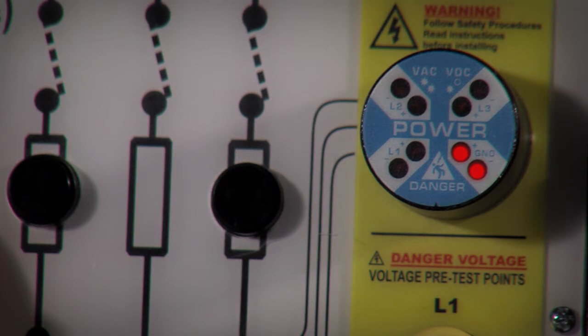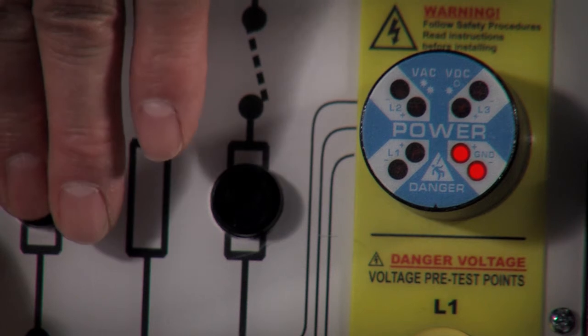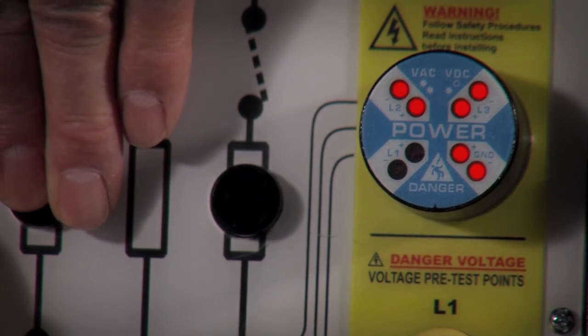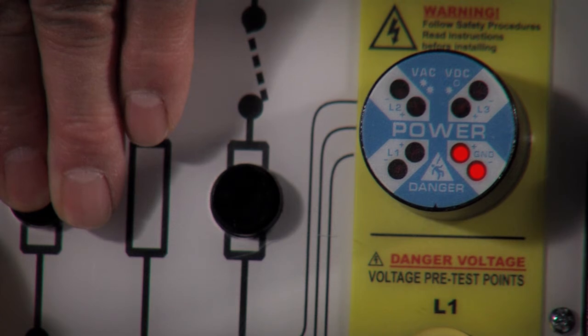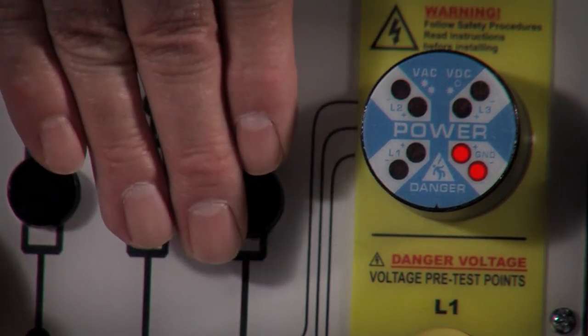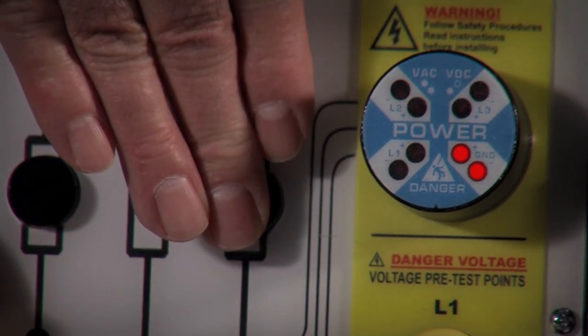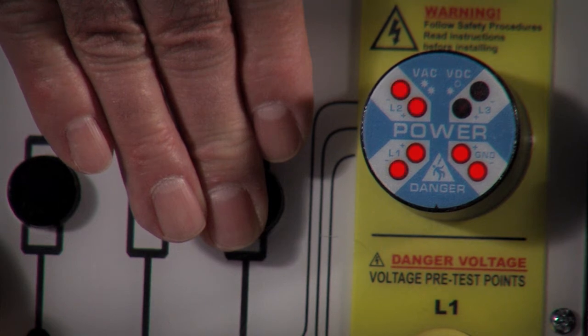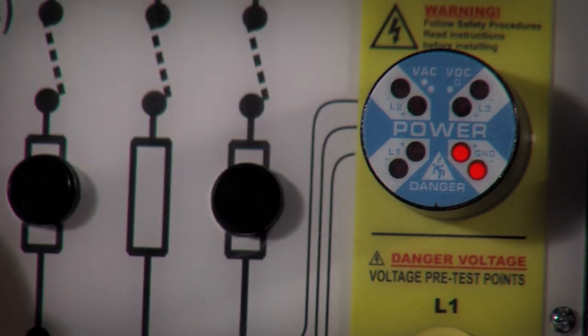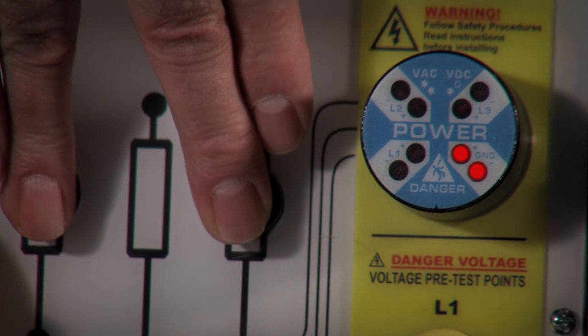Another common feature that these devices all share is an opportunity to show a blown fuse indication. Here we're representing a blown fuse on L1. This is what a blown fuse would look like on L3. And here's what it would look like if you ever had a stuck blade.